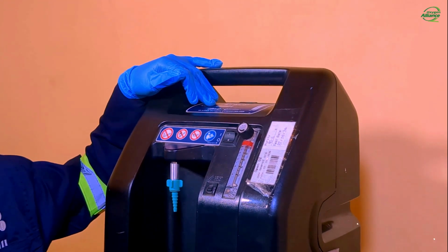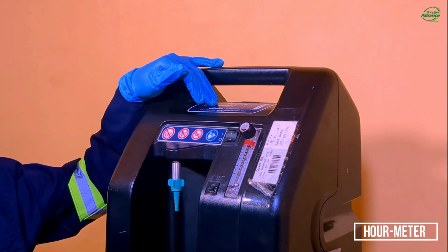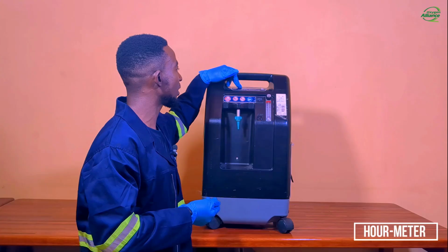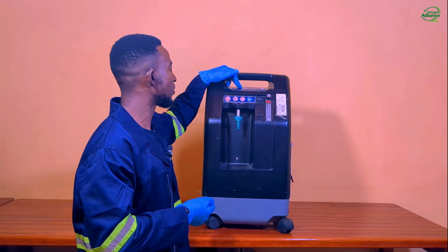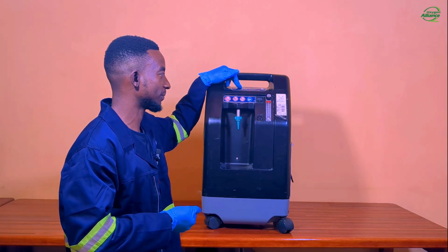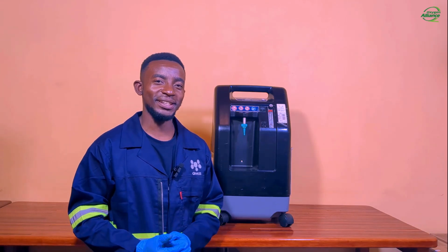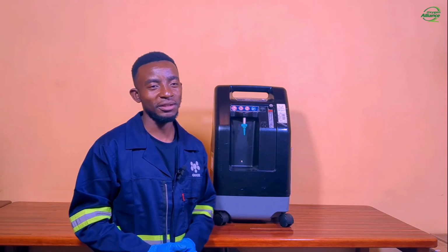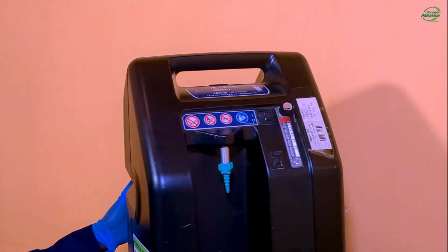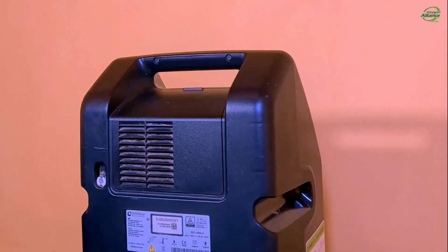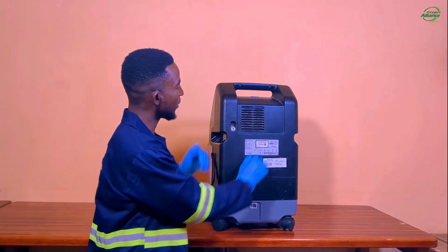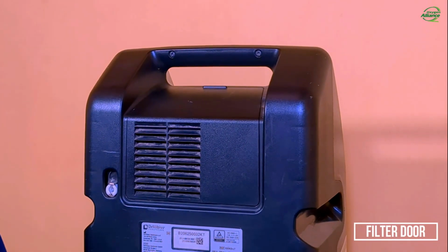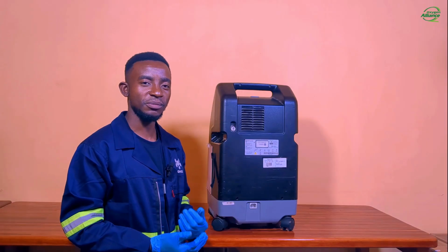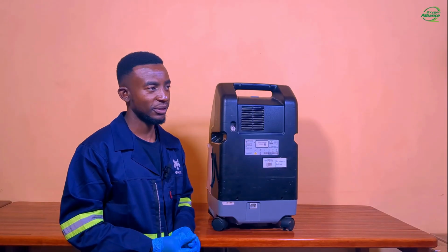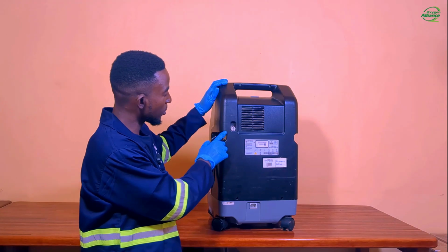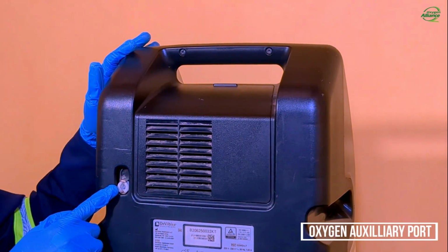We also have an hour meter. The hour meter is used to indicate the cumulative hours the oxygen concentrator has run. So let us look at the parts at the back of the concentrator. We have the filter door. So the filter door is going to give you access to the gross particle filter as well as the HEPA filter. We also have an oxygen auxiliary port.